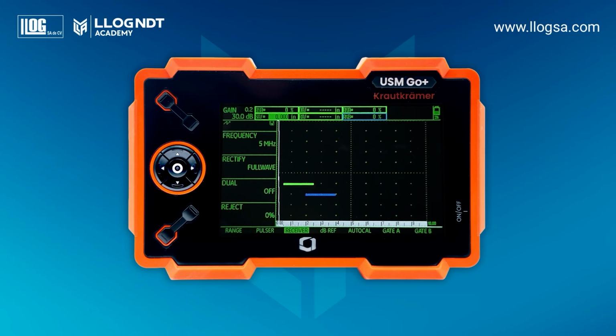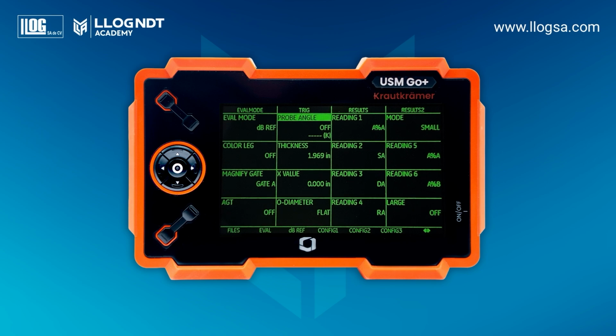Select the transducer frequency to use. For this example, we select 2.25 MHz. Wave rectification, full. Dual mode, off. Rejection, 0%. Gate height, 20%. Gate measurement mode, peak. In the second level functions, we configure refraction angle, 70 degrees. In automatic mode, the K value is adjusted, which is the tangent of the selected angle. Thickness, 4 inches.